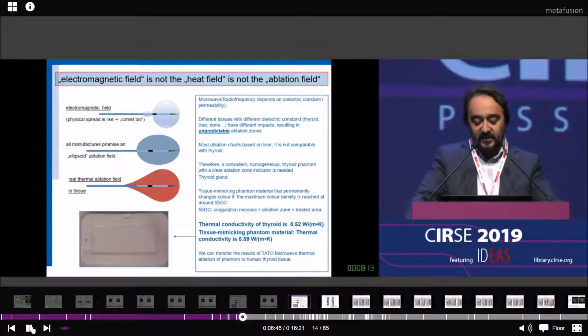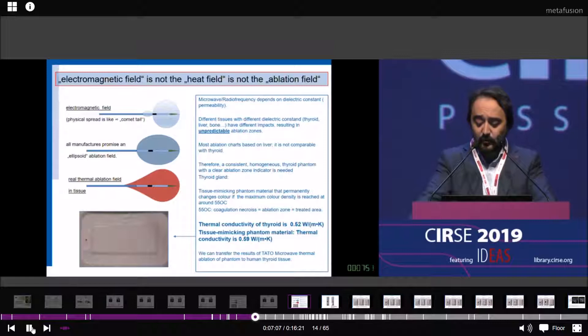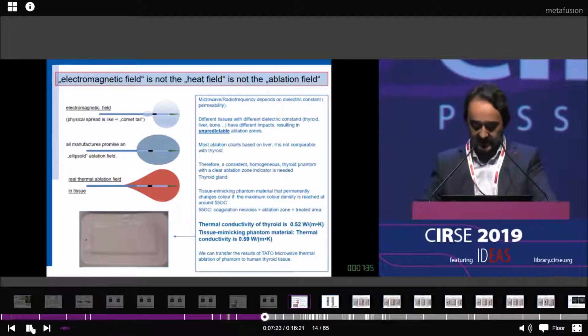This shows the electromagnetic field and the thermal field. All manufacturers promise an ellipsoid field, but that's not true — you always have a comet tail effect. Therefore, we checked the system using a tissue-mimicking phantom with the same thermal conductivity as thyroid: 0.5 for thyroid and 0.59 for the tissue-mimicking phantom. This allows us to transfer the results of TATO microwave thermal ablation from phantom to human tissue in solid nodules.